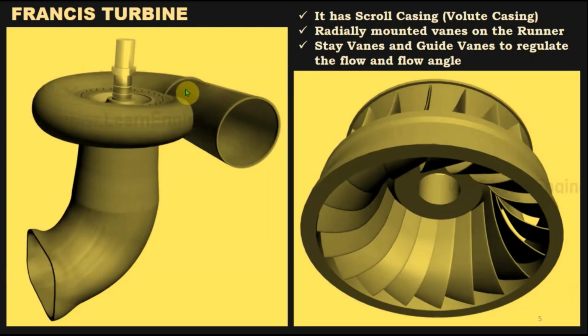There are different types of draft tubes available, and this is one of them. If you consider this peculiar shape of the scroll casing, you can understand that the flow area, that is the sections of this spiral tube, will keep on decreasing from the inlet to the exit. So the flow area reduces as water flows through this spiral casing. That is a hydraulic function. It essentially converts the pressure energy of water into kinetic energy as the flow progresses through the casing.